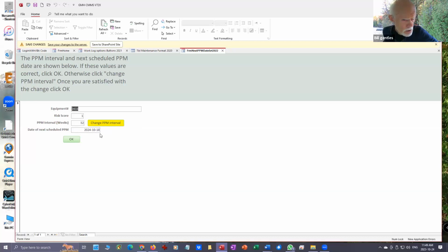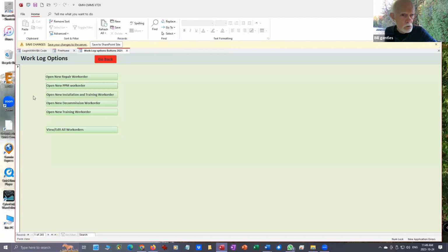Maybe it's a leap year next year. Anyway, so 52 weeks from today is October the 18th, 2024. And now you can click OK, and that will be stored as a reminder for when the next PPM is going to be due. So I click OK, and it goes back to this screen here.